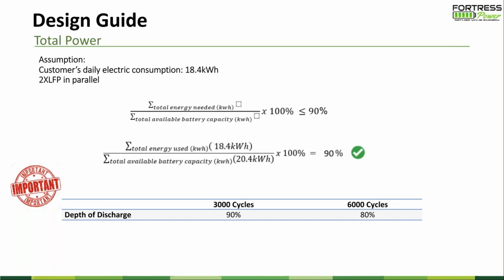We want to size the battery bank for just 90% depth of discharge. That's why your total energy divided by the total available energy in the battery bank, times 100%, should be less than 90%. Don't try to discharge the battery 100%. It's going to kill the battery quicker and shorten its life cycles. It doesn't pay off, right? If you discharge the battery 100% every time, it probably gives you around 2,000 cycles, and then the battery is gone. If you discharge to 90% or 80%, it's going to give you 3,000 cycles and 6,000 cycles, as I mentioned here.